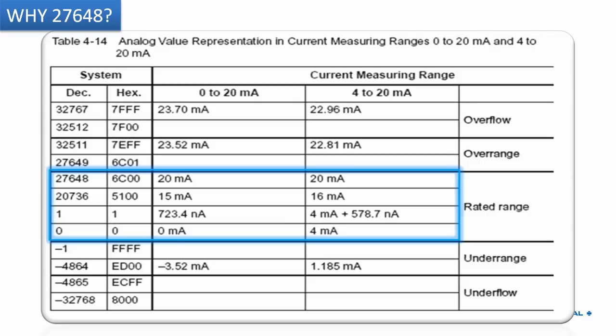Why 27648? Remember — for 4 to 20 milliampere, if the current value is less than 4 milliampere that is an underrange or underflow. To detect that, Siemens reserved some space from the total value range. For overflow — if the value exceeds 20 milliampere — they also reserved some values to sense that. So for underflow and overflow, some values from the whole range are reserved, and the working range between 4 to 20 milliampere is mapped to 0 to 27648.